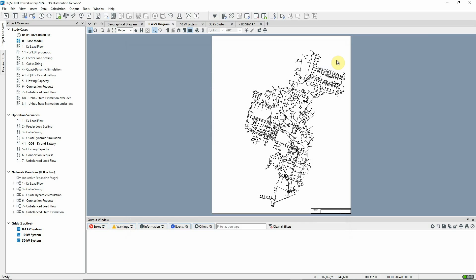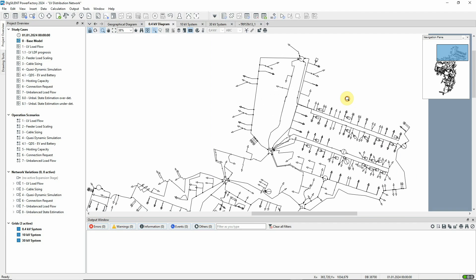Now, we'll close an interconnection and force the network to run in a mesh. We'll look at the detailed single line diagram for this particular substation.